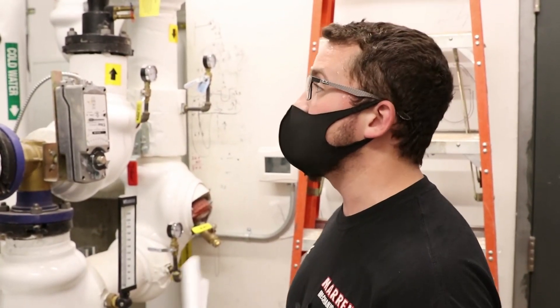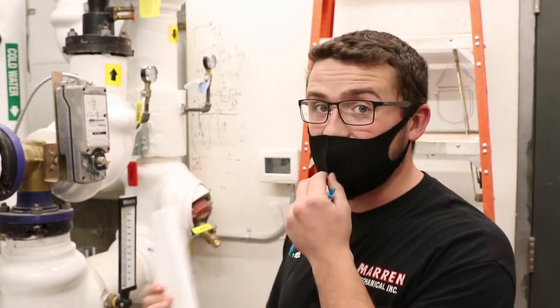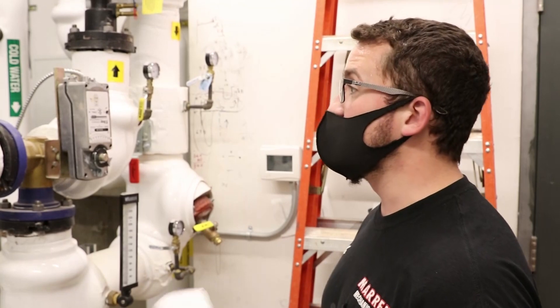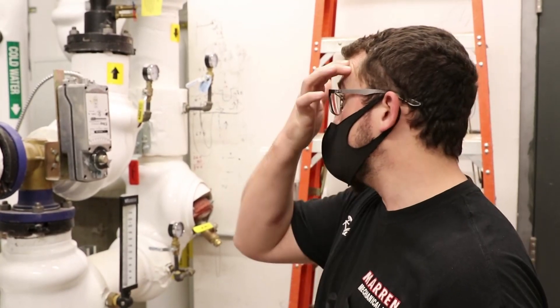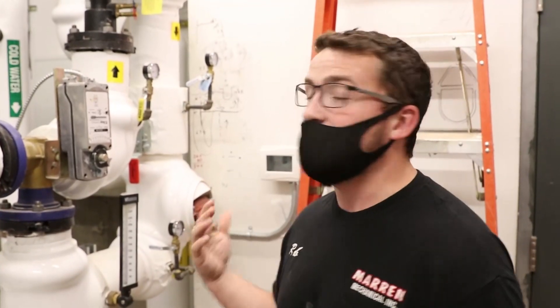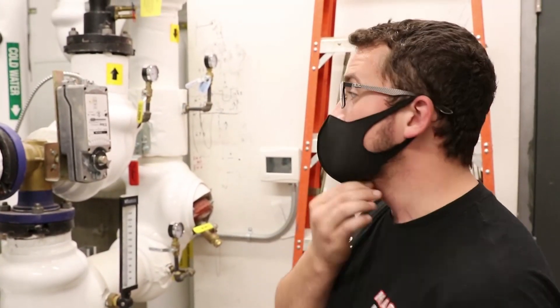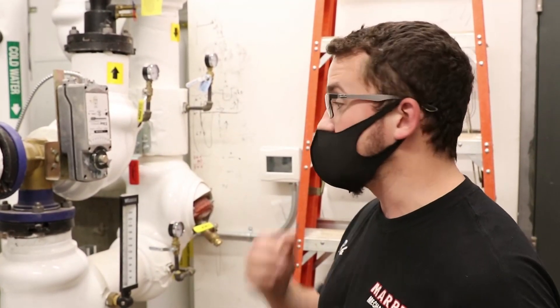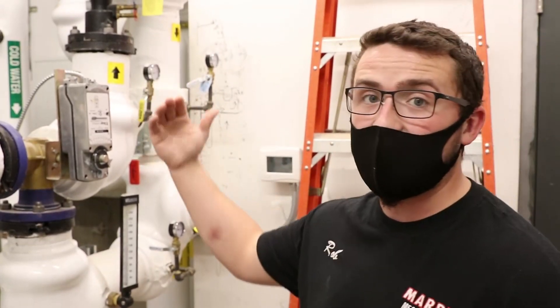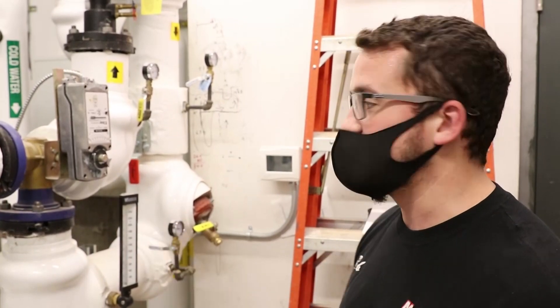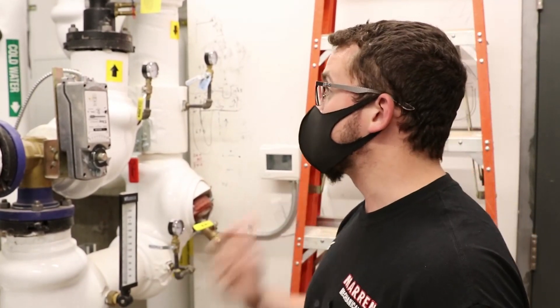The best way, if you're having an issue with this and you need to clean those, you would look for poor performance. If this water heater over time begins to struggle more and more with making temperature or eventually is not capable of reaching temperature anymore, you should call for service to troubleshoot and rule out other issues. But at that time, if there are no other issues, it may become necessary to flush out the inside of the tank and clean either the inside of the tank or the heat exchanger, which could be done by a service company.